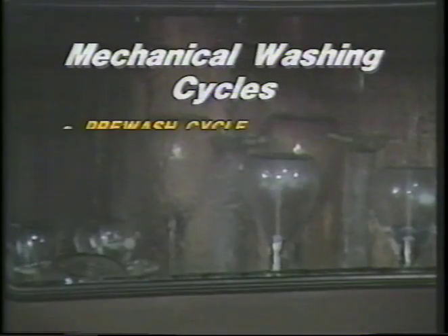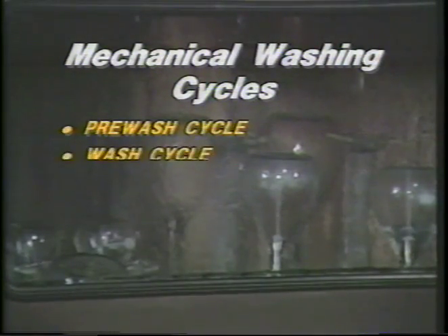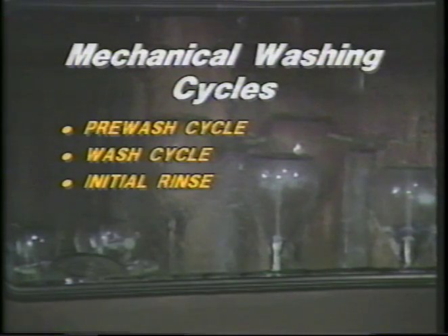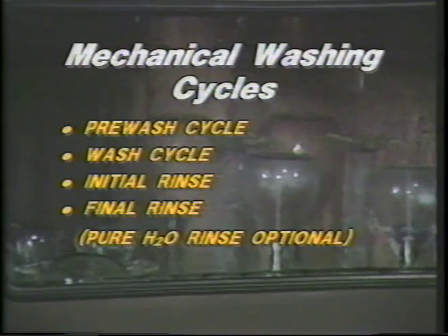There are usually 5 different phases employed in mechanical washing cycle. They are the pre-wash cycle, the wash phase, an initial rinse, which is usually the same temperature as the washing phase to remove detergent, and a final rinse. The final rinse is essentially an insurance policy in conjunction with the first rinse for removal of residual soil.